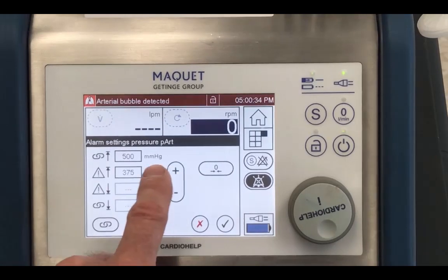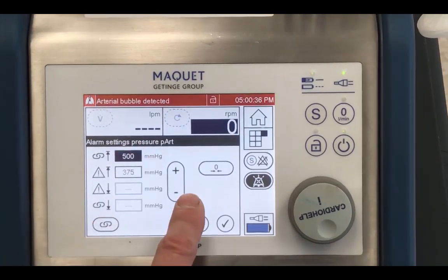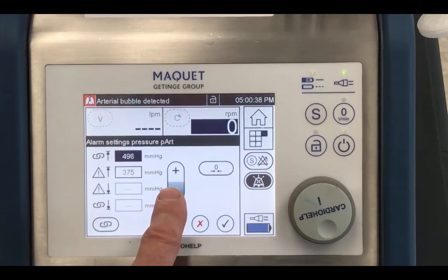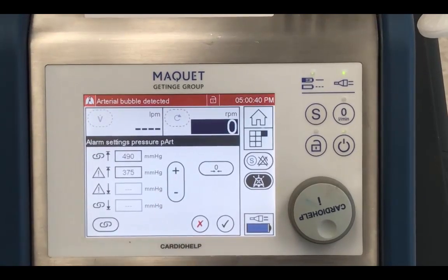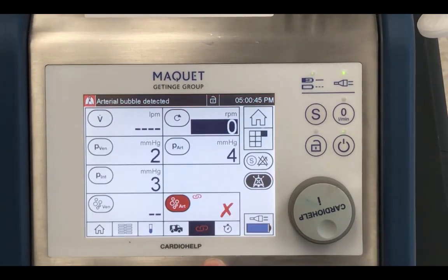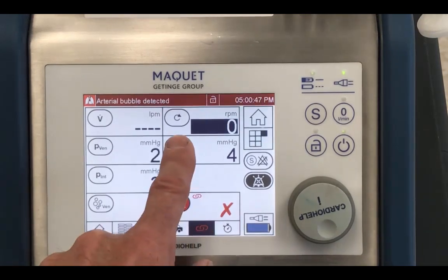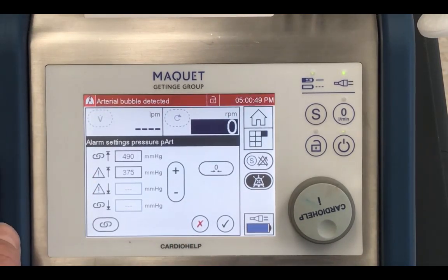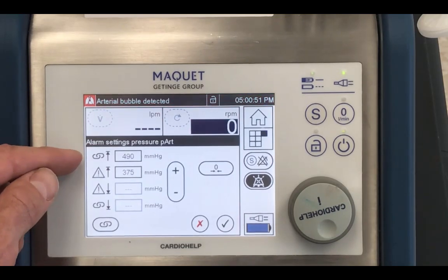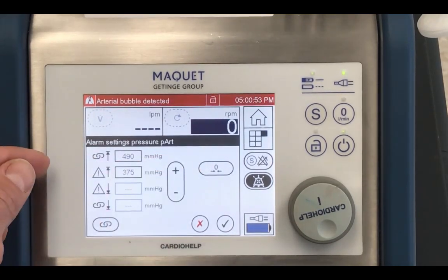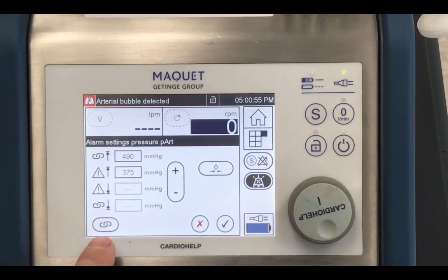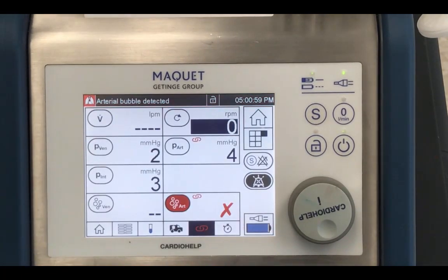Let's turn that 500 down to 450, or 490 is fine. Hit the green checkbox, and I will have changed the limits. They're now 375 and 490. If I want this pump to slow down its RPMs when the pressure reaches 490, I need to turn on the intervention and hit the arrow. Hit the checkbox to enter that.